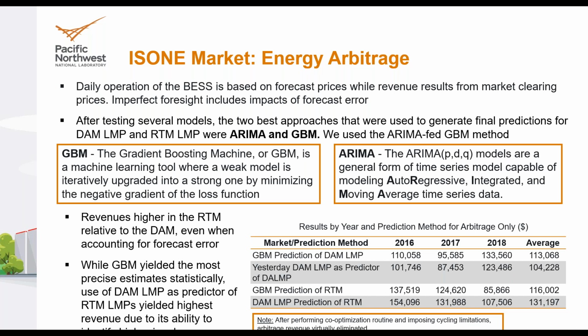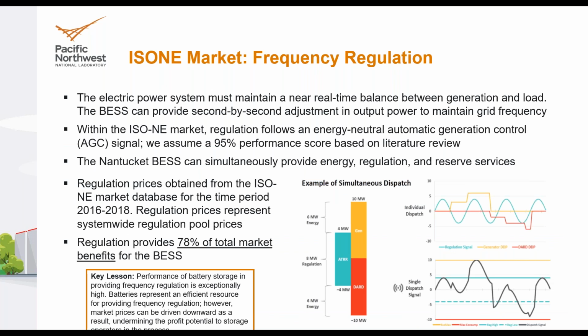It's important to note there were fairly significant cycling limitations, only about 150 cycles per year. Once you build that in, it actually eliminated arbitrage as a value stream. With this battery system, a 48 megawatt-hour system, you couldn't provide more than 7,200 megawatt-hours of energy on an annual basis. So frequency regulation was the high-value item.